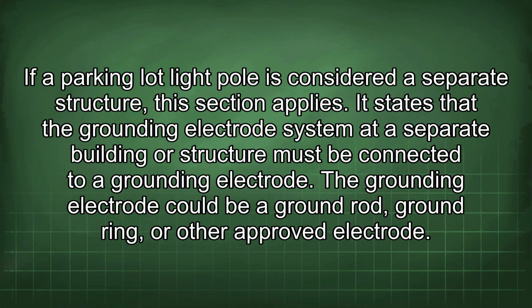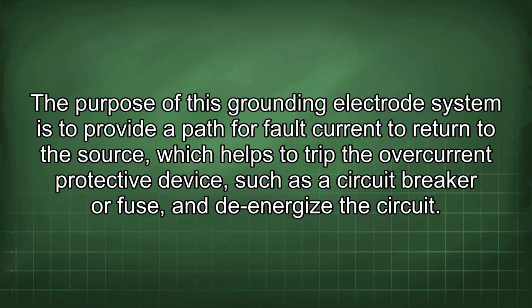If a parking lot light pole is considered a separate structure, this section applies. It states that the grounding electrode system at a separate building or structure must be connected to a grounding electrode. The grounding electrode could be a ground rod, ground ring, or other approved electrode. The purpose of this grounding electrode system is to provide a path for fault current to return to the source, which helps to trigger the overcurrent protective device, such as a circuit breaker or fuse, and de-energize the circuit.